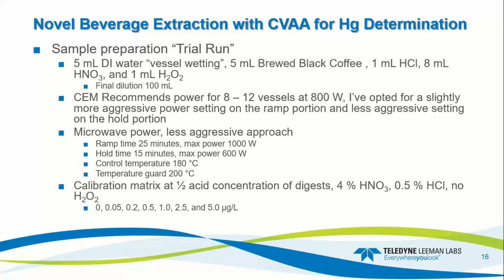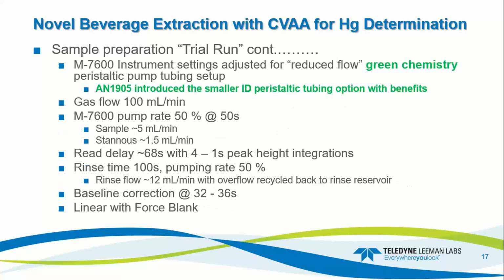My calibrations were blank, 0.05, 0.2, 0.5, 1.0, 2.5, and 5.0 ppb for this experiment. For the M7600 instrument settings, I adjusted these for the reduced flow, or green chemistry, peristaltic pump tubing setup. This was first introduced with application note 1905. Gas flows are at 100 mils per minute. My pump rate for the system was 50% with an uptake of 50 seconds, so about 5 mils per sample, and the stannous chloride was approximately 1.5 milliliters per minute. I should say 5 milliliters per minute on the sample at 50 seconds.